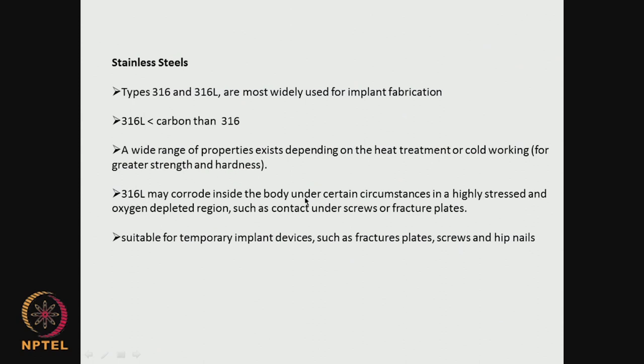Stainless steel can corrode inside the body, especially when stressed, when there is oxygen depletion, and when in contact with screws or fracture plates. So they are good for temporary implant purposes — fracture plates, where the idea is once the fracture is healed they can be removed, screws, hip nails. We call this more of a temporary implant.